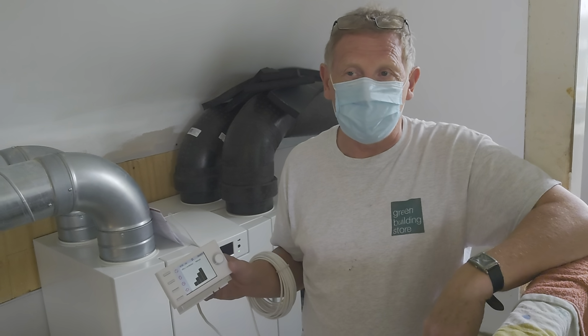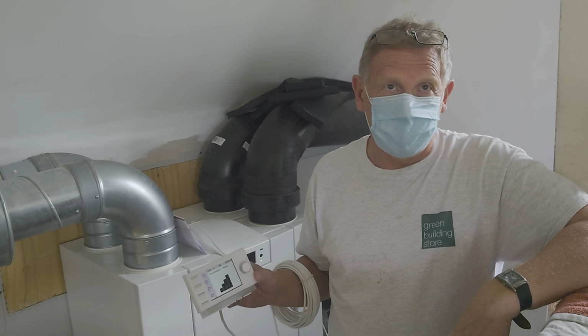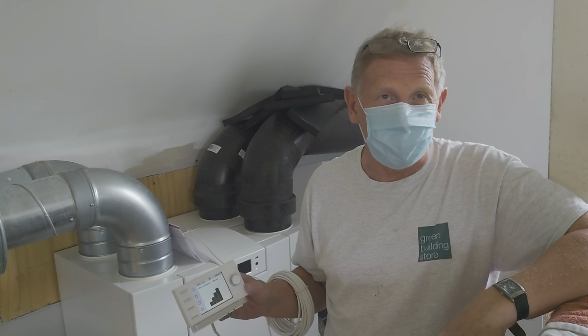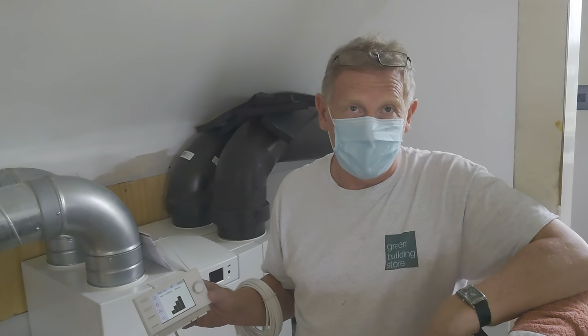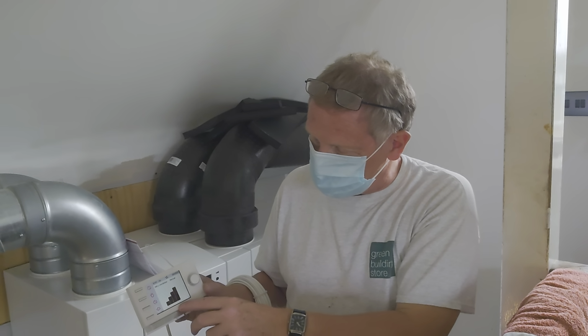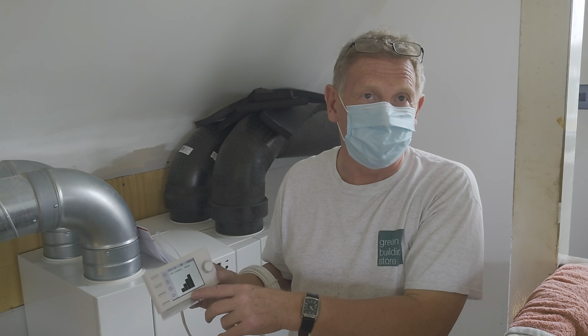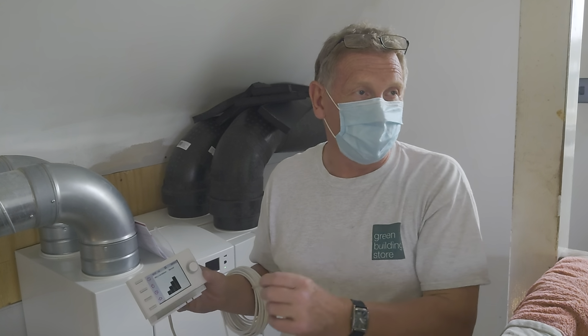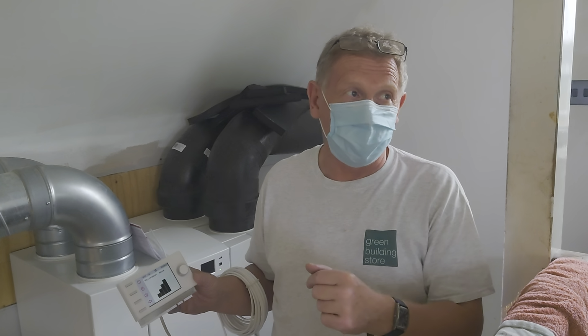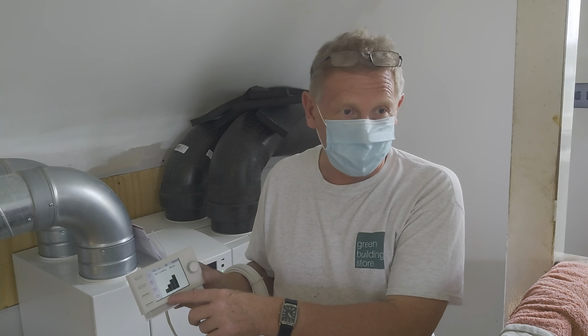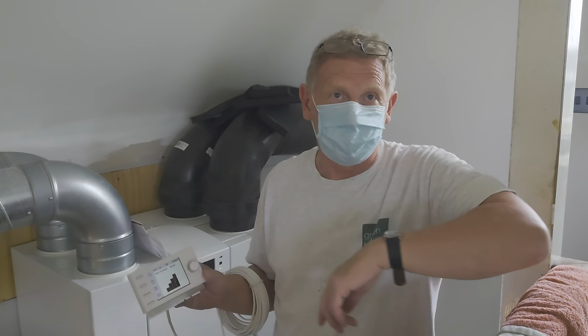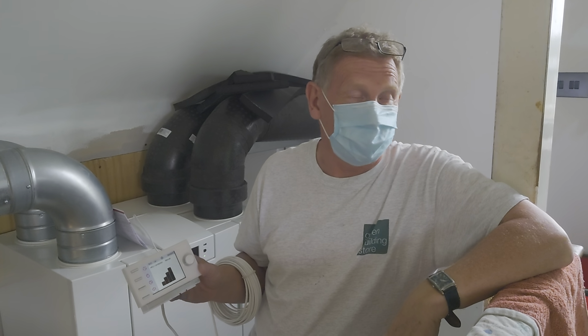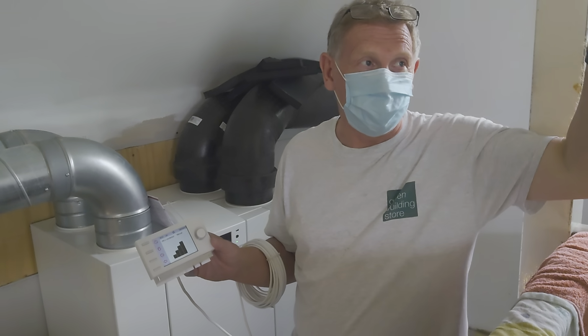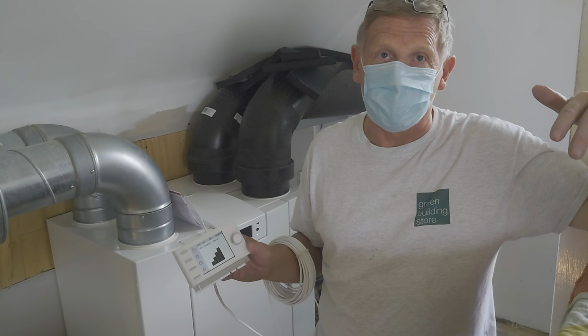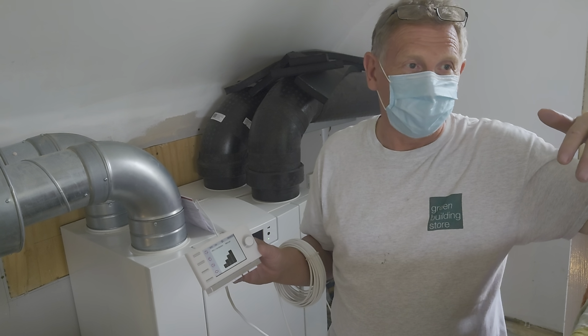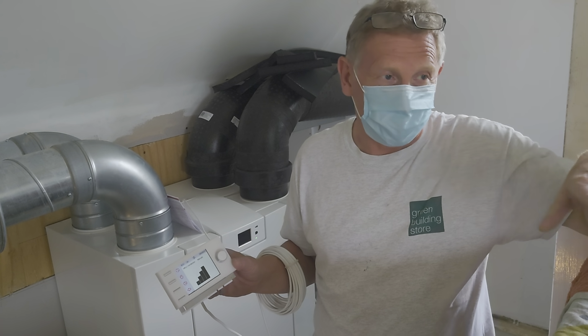If you think of the MVHR extraction, even on boost, it's still relatively low compared to a cooker hood. The only difference between each of those fan speeds is about 30% air volume—it's not like a cooker hood where you turn it up to boost and it doubles the fan speed, you're only turning the flow rate up by 30% for each notch. So even if you put your hand in front of that now, you'll struggle to feel the airflow—it might only be 20% of what your cooker hood can do.